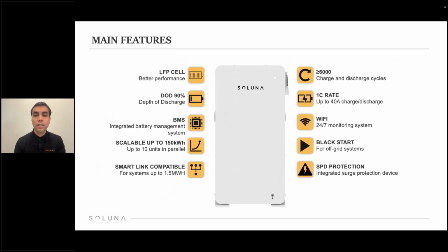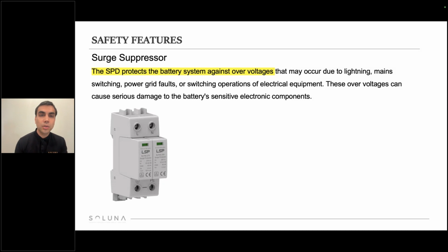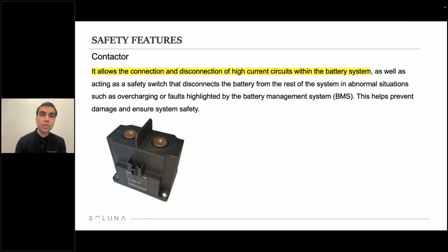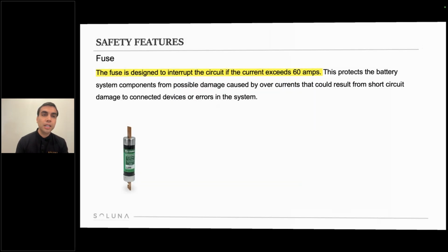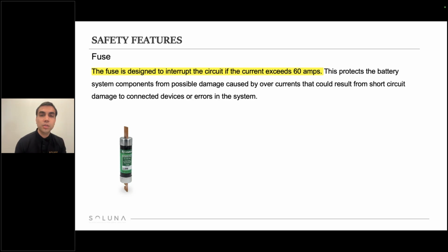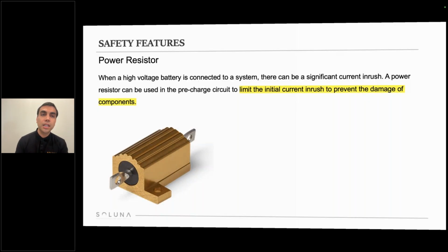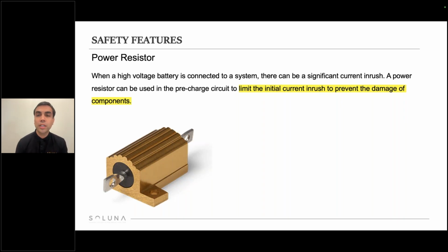With SPD protection, an integrated surge protection device, this will allow for protection against overvoltages. We have a contactor, which allows the connection and disconnection of high current circuits within the battery system. It has a fuse that is designed to interrupt the circuit if the current exceeds 60 amps, and it has a power resistor that limits the initial current inrush to prevent damage to components. When the inverter is turned on, there is an inrush coming into the battery, and the power resistor will prevent the damage of components.